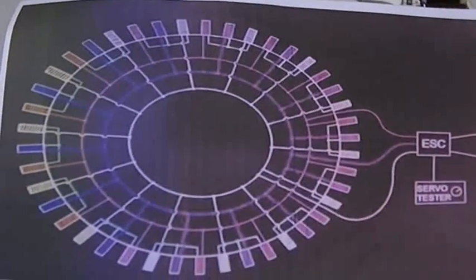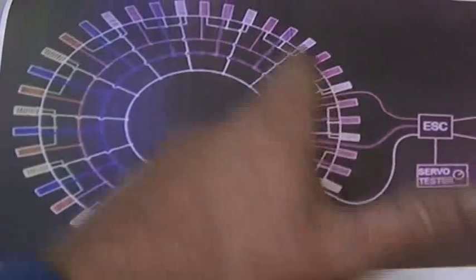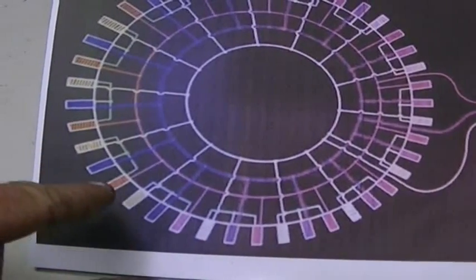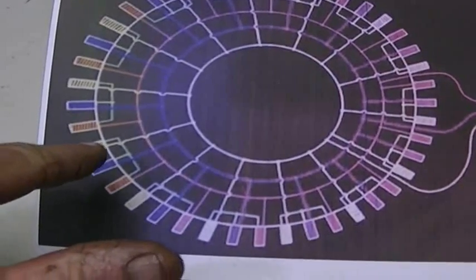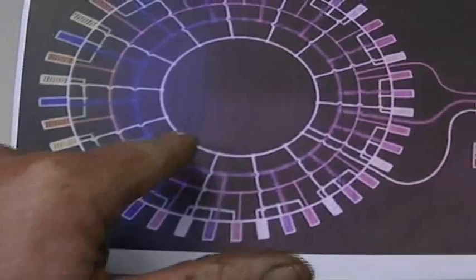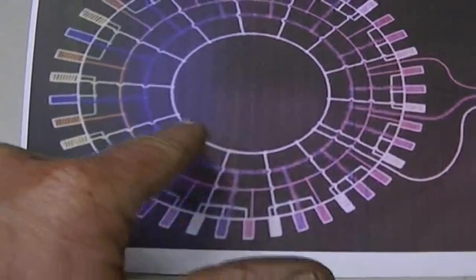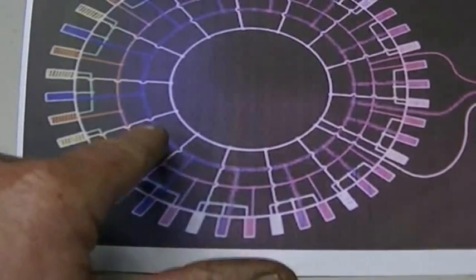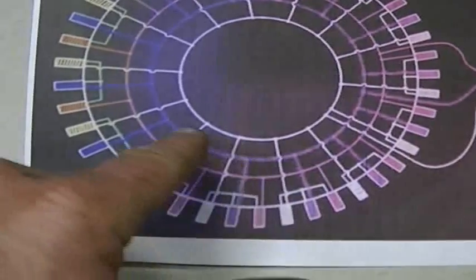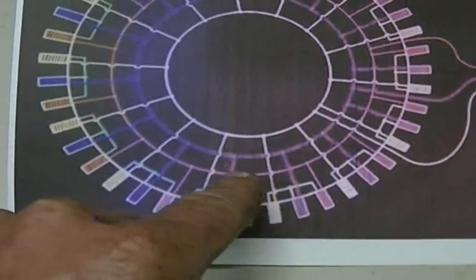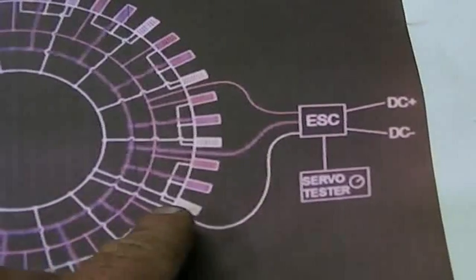This is the wiring diagram that we end up with. Looks like I've started to run out of ink, but anyway you can see how it works. Phase one, phase two, and phase three—the ends are all joined together. Then starts of each coil on each phase, so phase one will go to this ring here, they're all parallel connected. Phase two to the second ring, the blue's changed to pink because we've run out of ink.